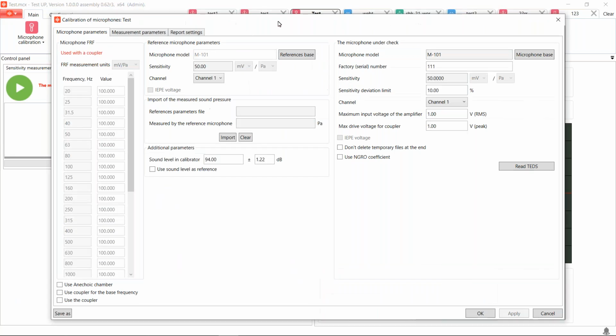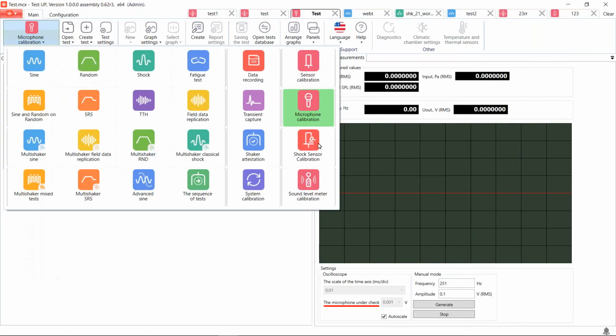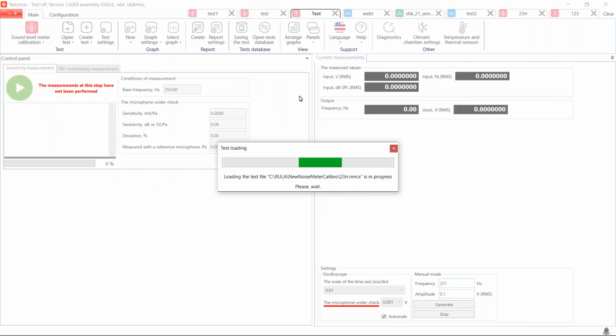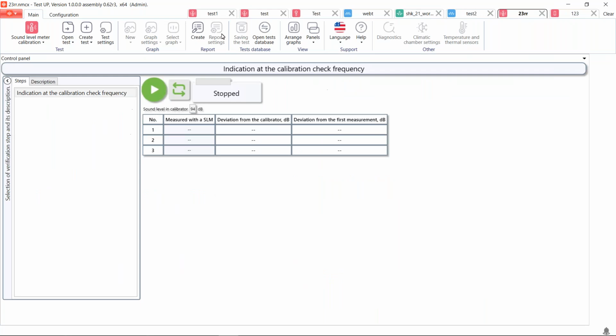Let's open it. Well, the main difficulty in calibration of the sound level meters is that every sound level meter has its own guide of calibration, including certain steps of this procedure. And the variety of sound level meters is so wide that it is hard to imagine that any software includes all of them. What we did, we tried to make the process of sound level meters calibration as user-friendly as possible and organized the interface in a special way.